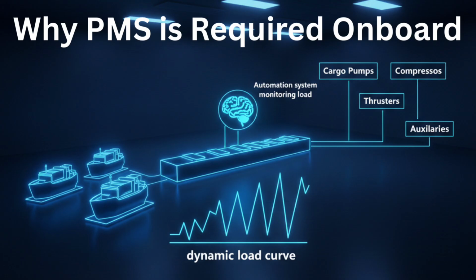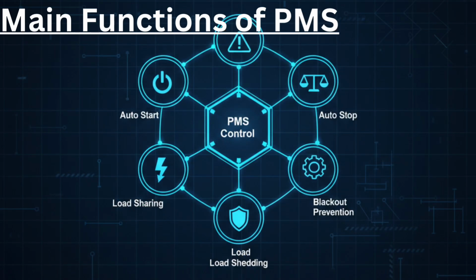Understanding PMS operation is critical for all ship engineers, whether on watch or troubleshooting in the control room. The main functions of PMS include automatic generator start and stop, load sharing, load shedding, blackout prevention, and synchronization. These functions work together to keep the ship's electrical system stable under all conditions. The PMS continuously monitors voltage, frequency, generator load, and reactive power. When load rises suddenly, it starts standby generators and synchronizes them automatically. When load falls, it disconnects generators to save fuel.